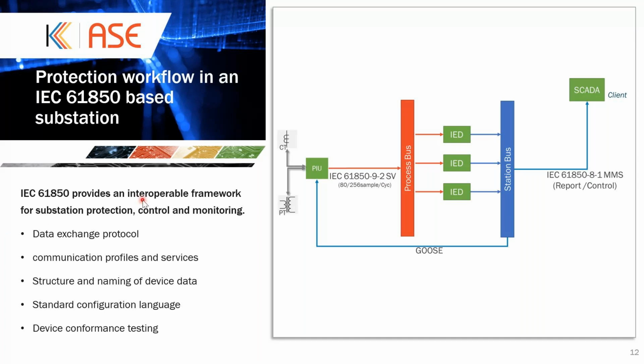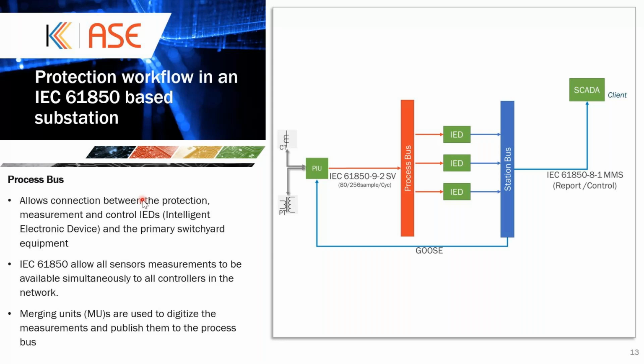And so we'll just quickly go through the process bus part of the IEC 61850 standard. The process bus allows connection between the protection, measurement, and control IEDs and the primary switchyard equipment. IEC 61850 allows all sensor measurements to be available simultaneously to all controllers in the network. There are MUs, merging units, which are used to digitize the measurements and publish them to the process bus. We have a very well defined specification that clearly says how this data transmission happens, and how merging units are used to publish them to the process bus.